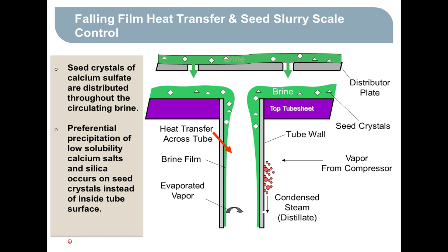Now you'll see some little dots suspended in the brine. Those are meant to represent seed crystals. And seed crystals are basically little crystals of calcium sulfate that are distributed throughout the brine that's circulating in the evaporator. And why are these little seed crystals in there? They're there because they provide a place for any low solubility salts which want to come out of solution, like calcium sulfate, calcium carbonate, calcium phosphate, silica. Any of those low solubility calcium salts are going to precipitate out fairly quickly in the evaporator, but instead of precipitating on the heat transfer surface as scale, they precipitate preferentially on the seed crystals, and the seed crystals grow larger. So those seeds are really there to keep the evaporator tube from scaling.